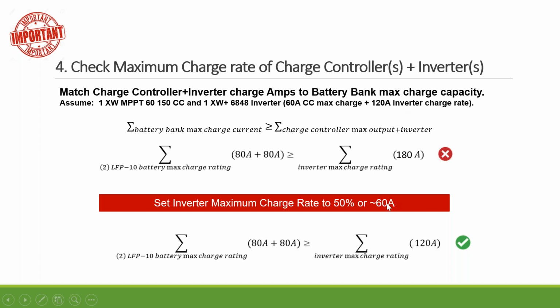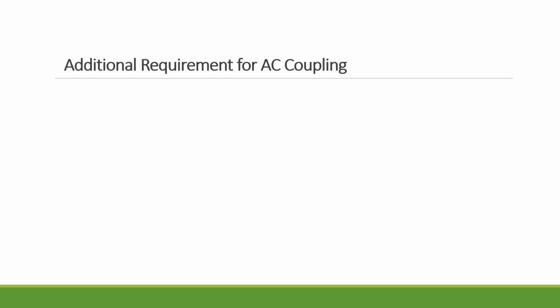But on the inverter, you can set up the charging rate. You can reduce the charging rate. In this case, you can reduce it to 50%. That way the inverter can only charge the battery at a maximum of 60 amps. So altogether, combined at full capacity, the charge controller and inverter can charge the battery at 120 amps, which is smaller than the 160 amps. Then the system operates very safely.